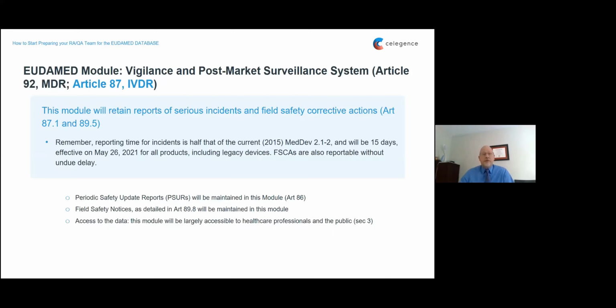Specifically, we are currently at 30 days under the current MEDDEV 2.12-1 guideline, and we will be moving to a 15-day reporting time for incidents and serious events, effective on May 26th of 2021. This includes legacy devices, and we should note also that field safety corrective actions will be reportable without undue delay. This is also the module where you will find reports of trends in non-serious incidents or expected undesirable side effects that could have a significant impact on the benefit-risk analysis for your devices.